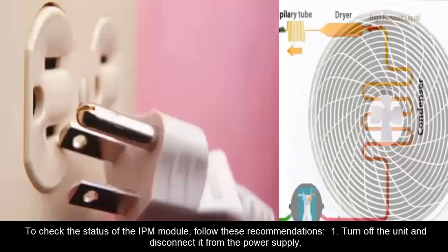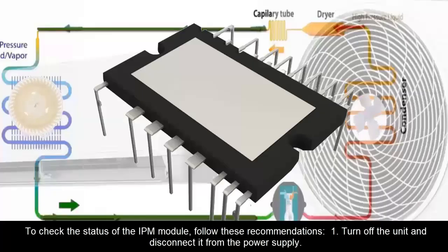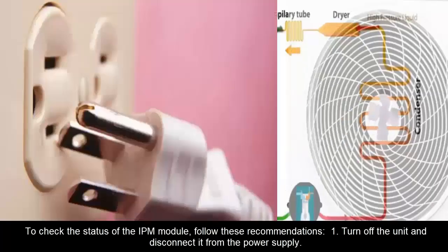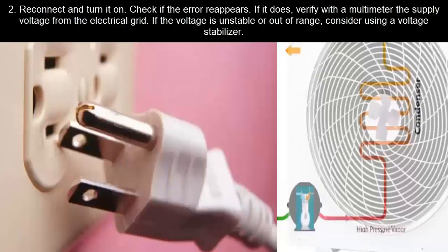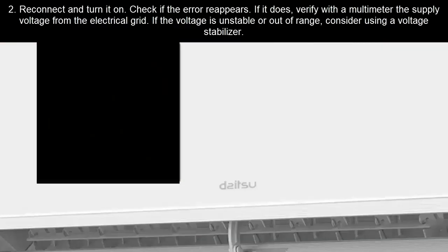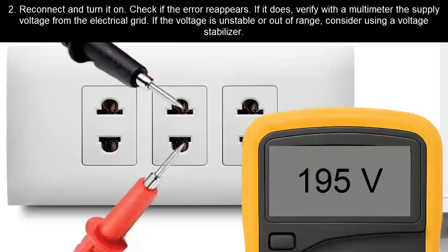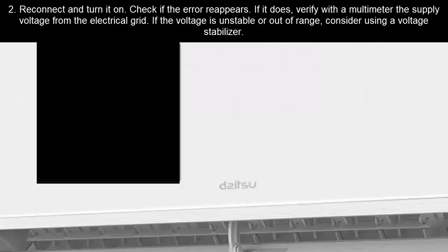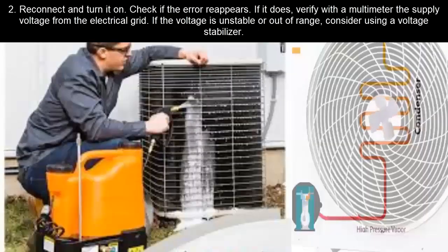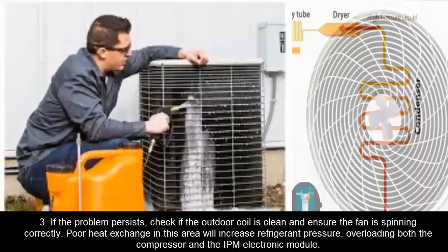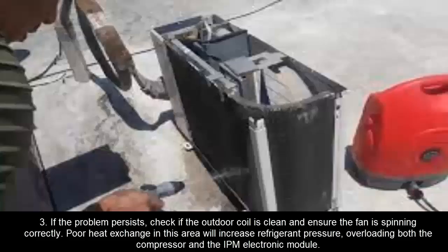To check the status of the IPM module, follow these recommendations. 1. Turn off the unit and disconnect it from the power supply. 2. Reconnect and turn it on. Check if the error reappears. If it does, verify with a multimeter the supply voltage from the electrical grid. If the voltage is unstable or out of range, consider using a voltage stabilizer. 3. If the problem persists, check if the outdoor coil is clean and ensure the fan is spinning correctly. Poor heat exchange in this area will increase refrigerant pressure, overloading both the compressor and the IPM electronic module.